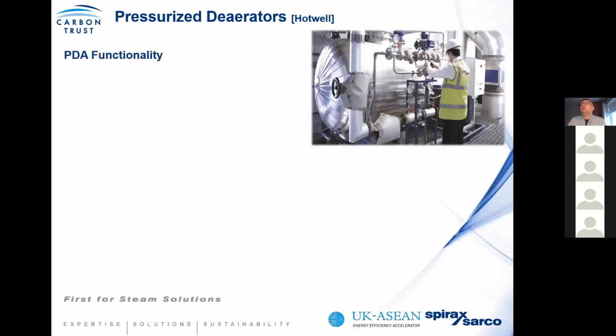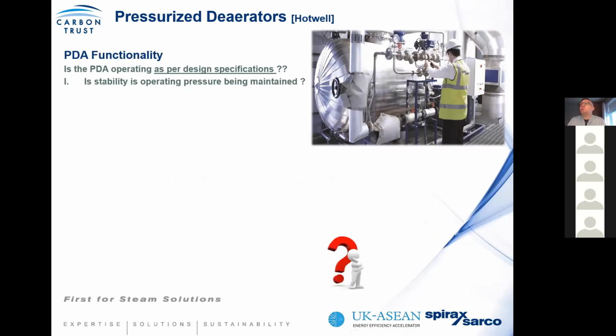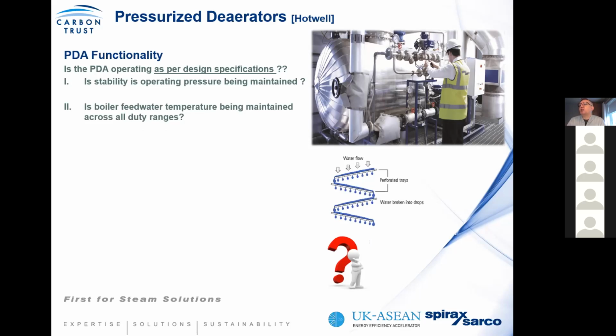Now let's talk about your boiler feed water system, or your pressurized deaerator, or hot well. We call pressurized deaerators a PDA for short. But it's important to understand the functionality of your feed water system. So is your deaerator or hot well operating as per design specifications? And often we find it's not the case. So you have to start thinking, do you see stability in pressure being maintained? For example, if your deaerator is designed to operate at 0.3 bar, is it a constant 0.3 bar, or does pressure fluctuate?